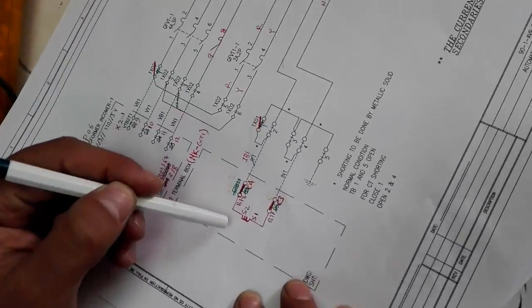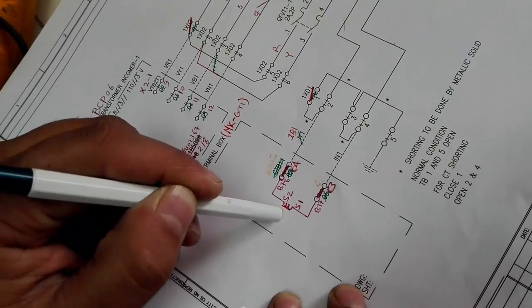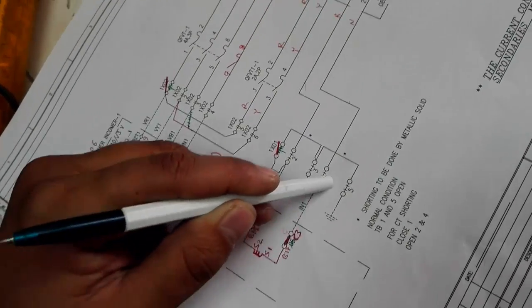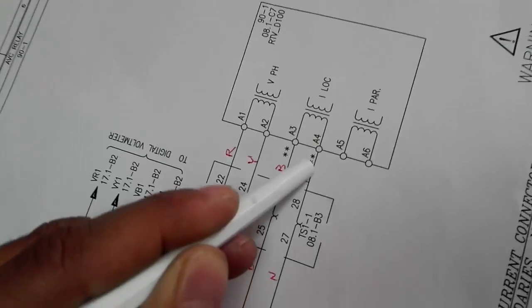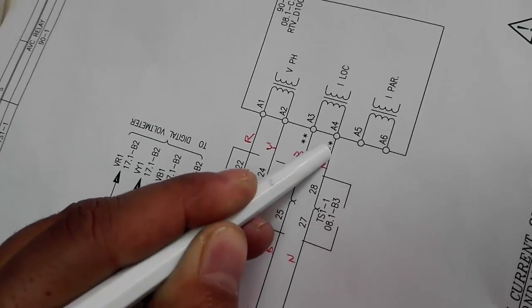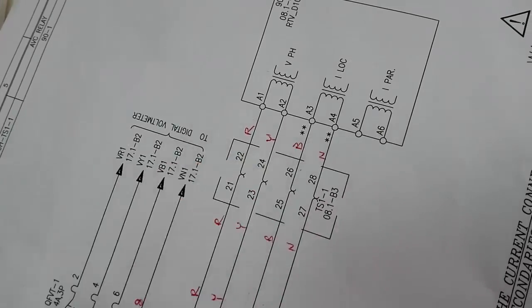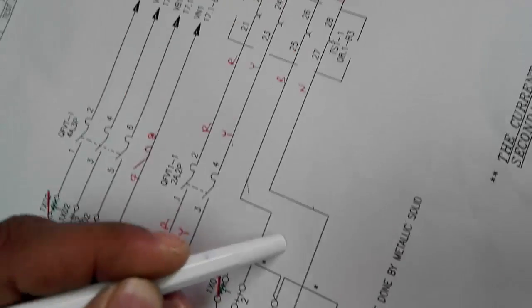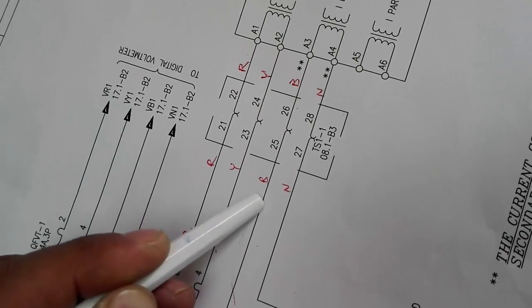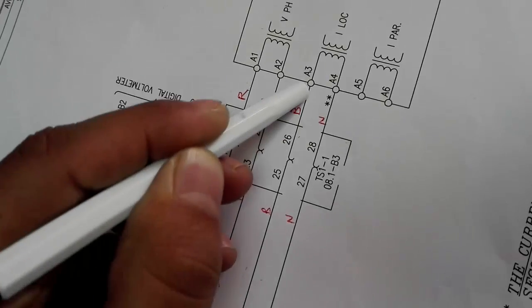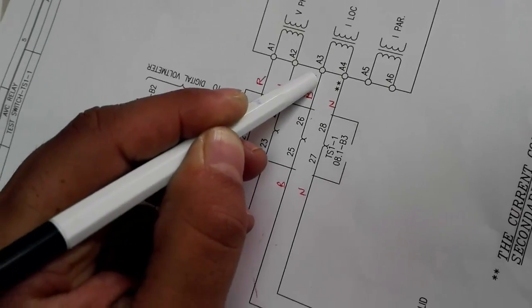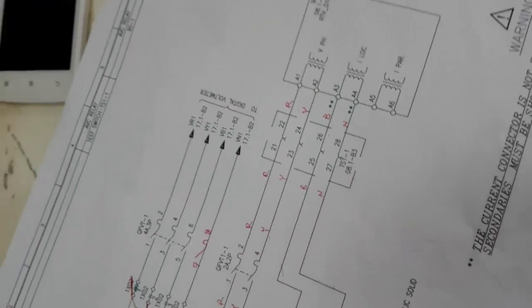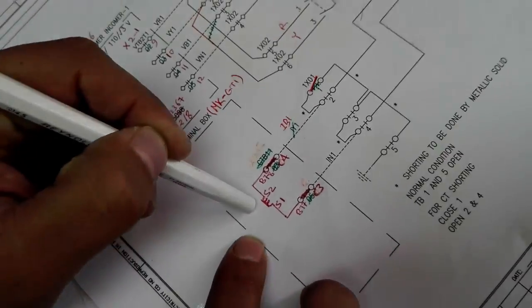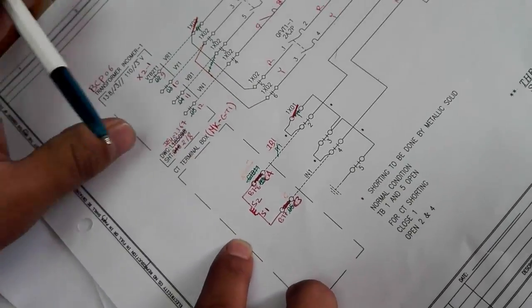See here, this S1 is connected to neutral and going to point 4 of our ZIV relay. And S2 is connected to B, the blue phase, and going to point 3. So it means that our connections are reversed. Now we will explain this point.